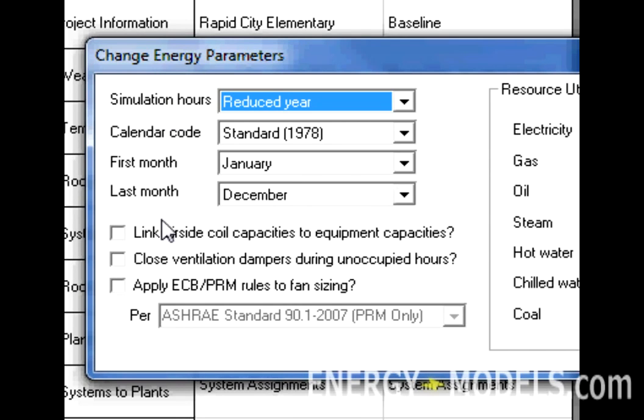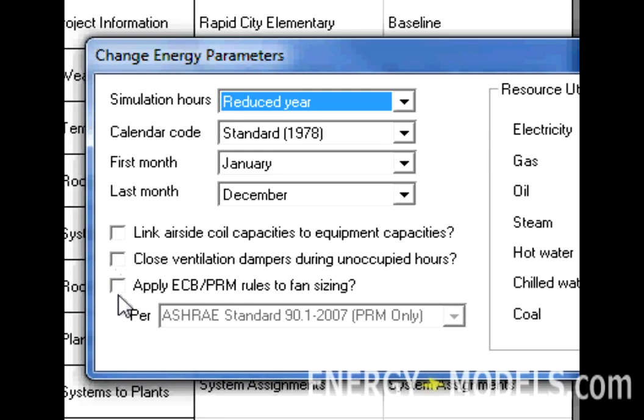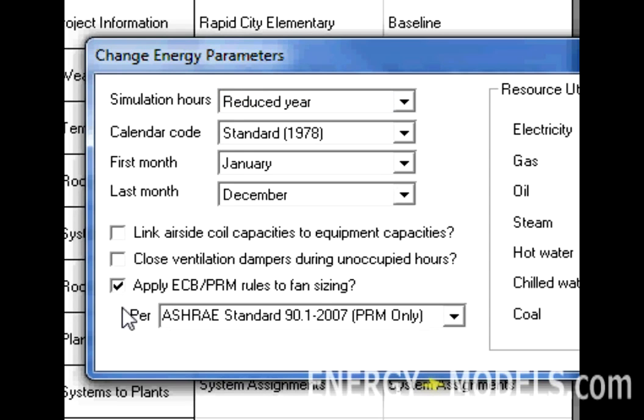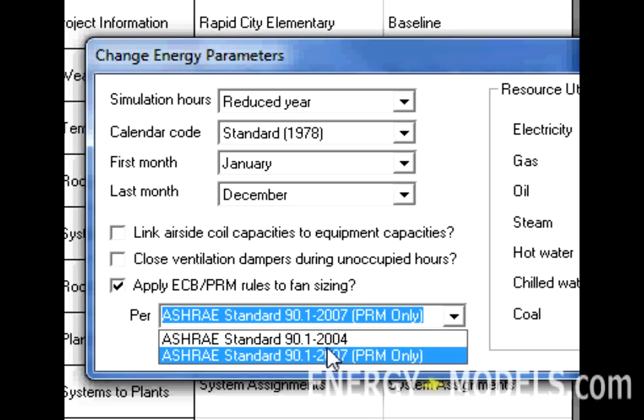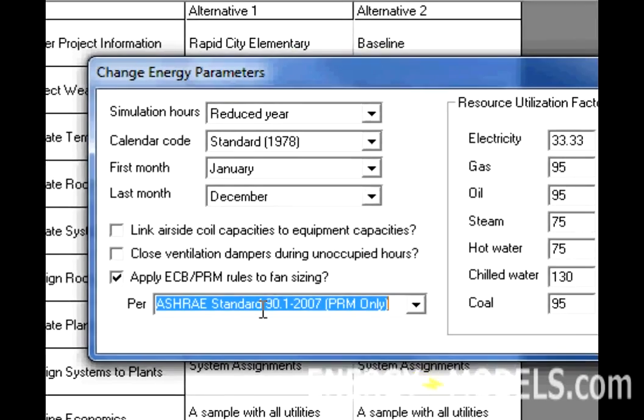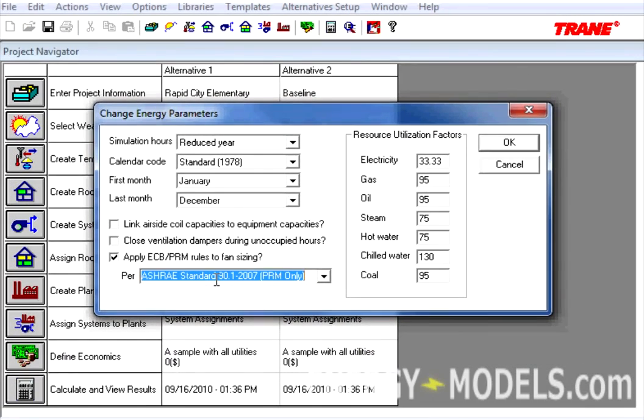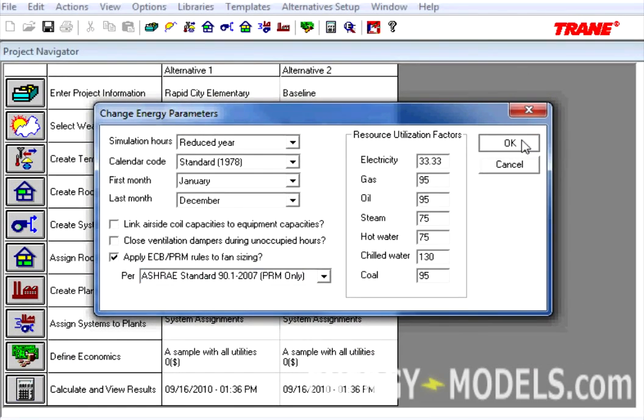Here, there's a new checkbox called Close Ventilation Dampers During Unoccupied Hours. This is brand new to version 6.2.6. However, when calculating a LEED file, which is what we'll be focused on here, we want to check the box Apply ECB slash PRM Rules to Fan Sizing. Here, we still have the option of 90.1.2004 or 90.1.2007. We'll stick with the 2007 option and click OK.